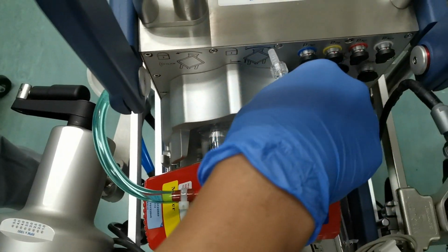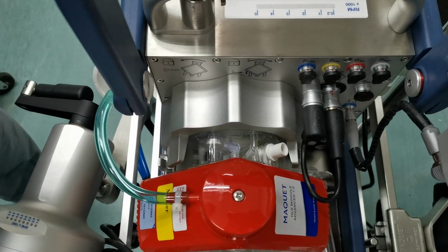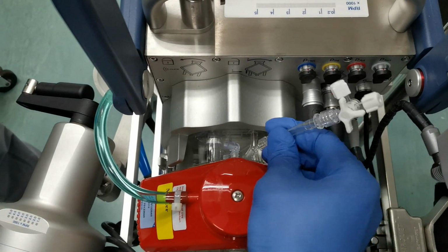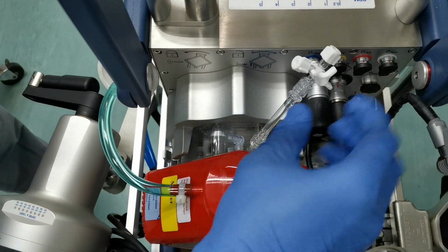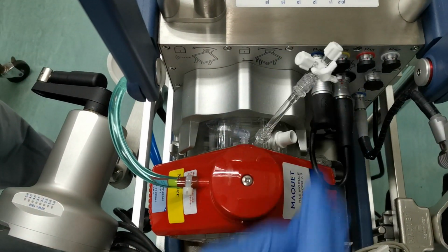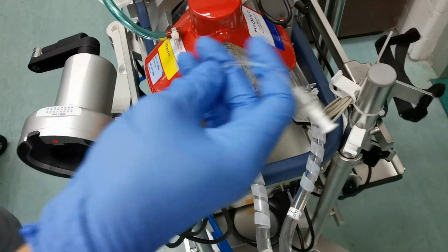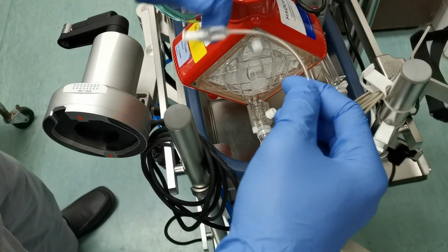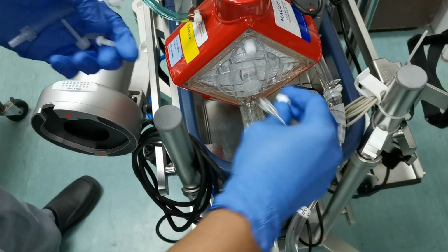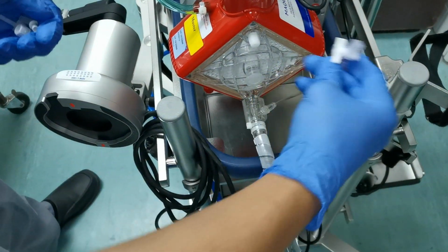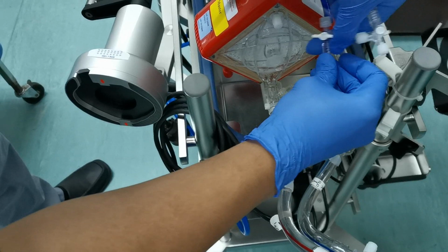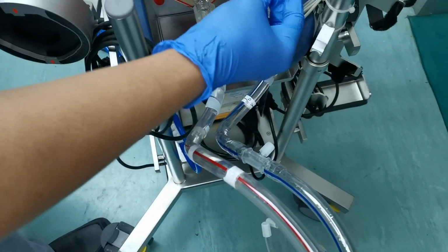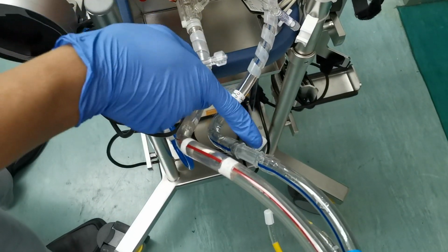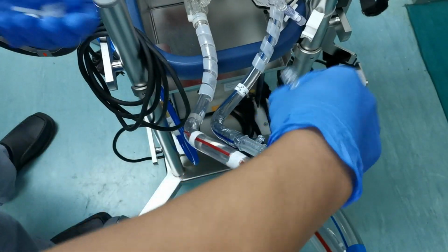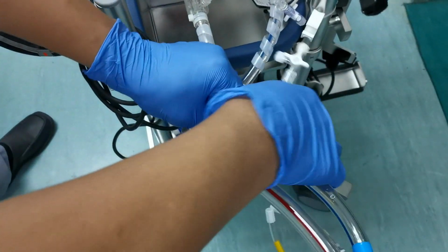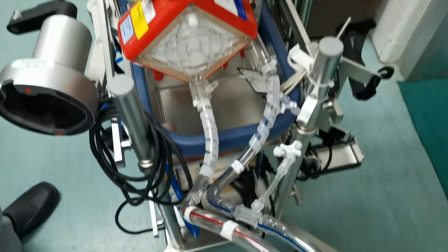Now add the 3-way tap with extensions toward its corresponding ports. One in the pre-oxygenator port, another one on the post-oxygenator port, and make sure to tighten all the caps and connections. And lastly, on the venous line. This 3-way tap with extensions can be used in cases when a continuous renal replacement therapy is needed.